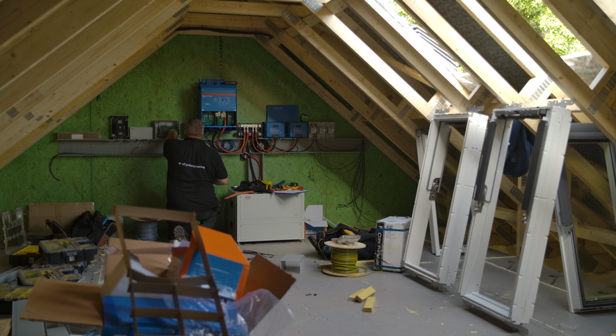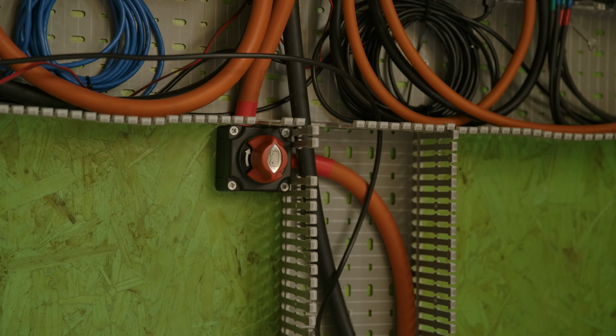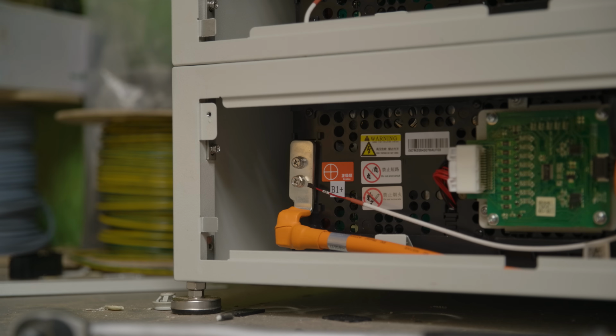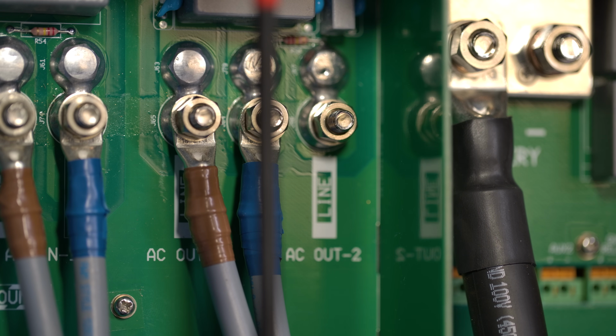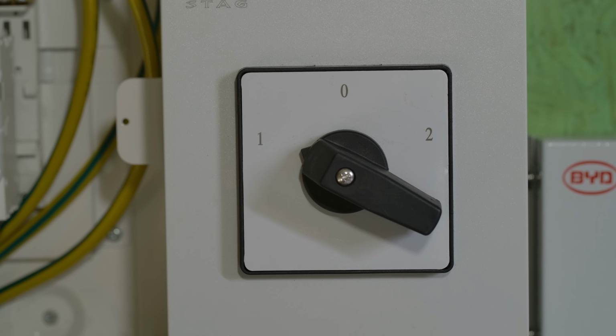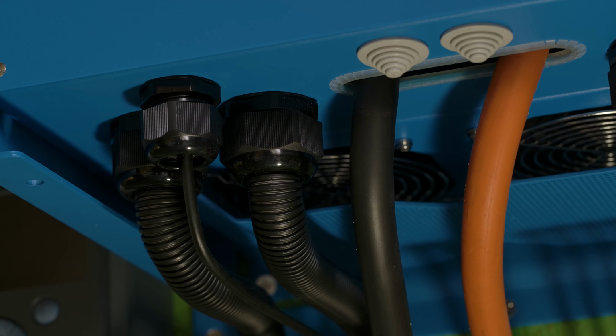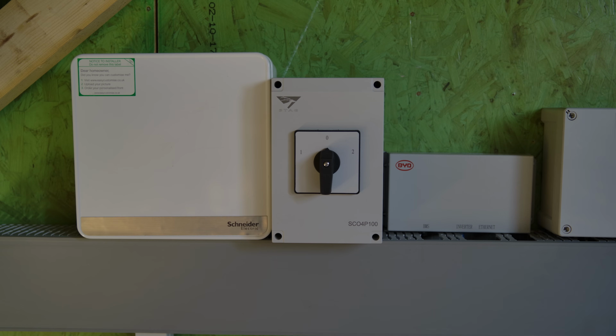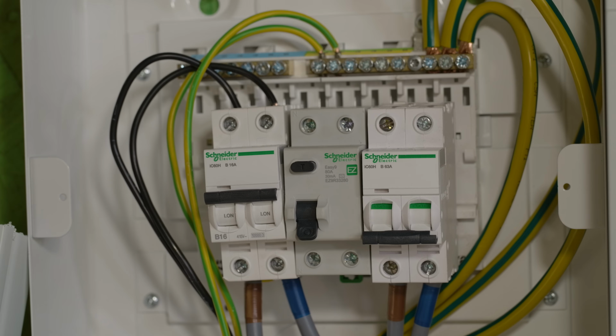Now that the DC system has been tested and is up and running, it's time to commission the AC side. 16mm tails from AC out 1 of the Quattro are wired to a master changeover switch. This switch has been put in place so that Jim can manually switch his house power over from either battery or generator if at all required. Then there is the local domestic consumer unit with MCBs to protect the cables both to the house consumer unit and from the generator.